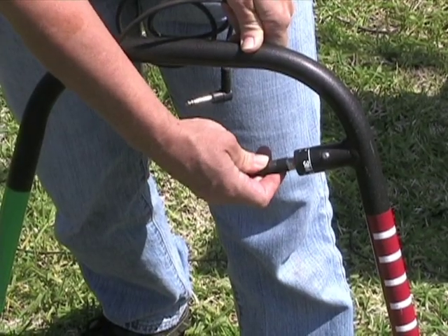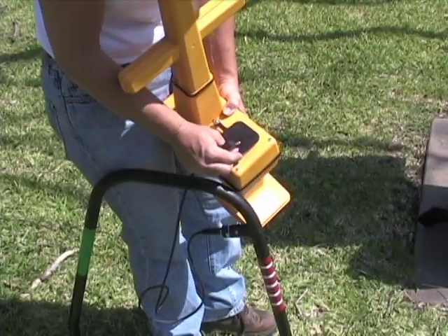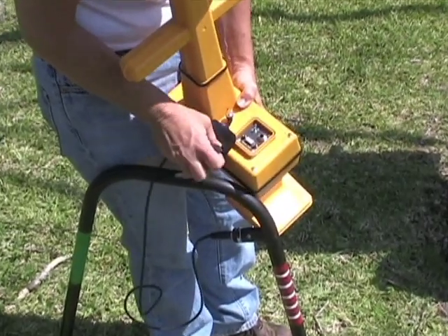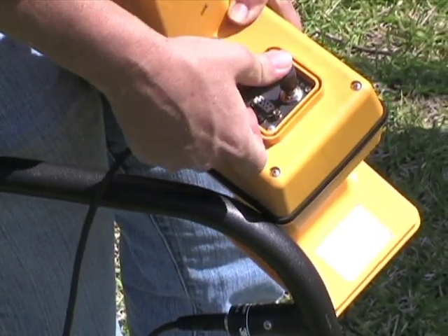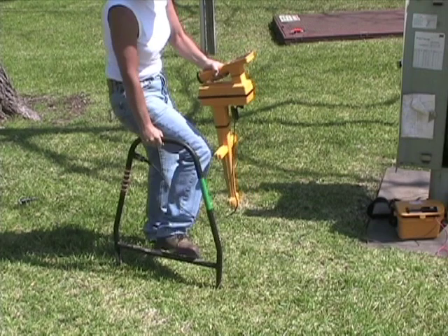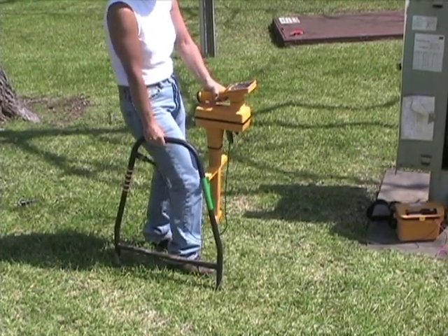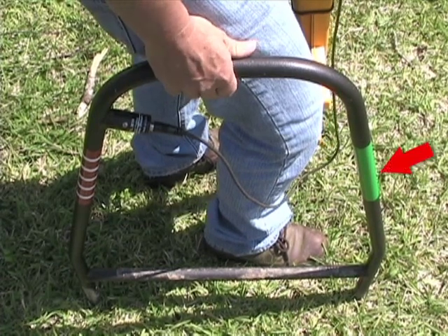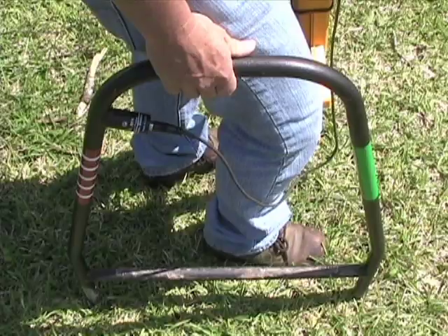Connect the 3-foot A-frame cable to the A-frame, making sure the cable is completely seated. Then plug the A-frame cable into the receiver. It connects to the bottom of the receiver through a 1/4-inch jack. When the spike points of the A-frame are pressed into the ground, the A-frame becomes a two-dimensional sensor that will detect the fault. The receiver will calculate whether the green-banded leg or the red-banded leg is closer to the fault.